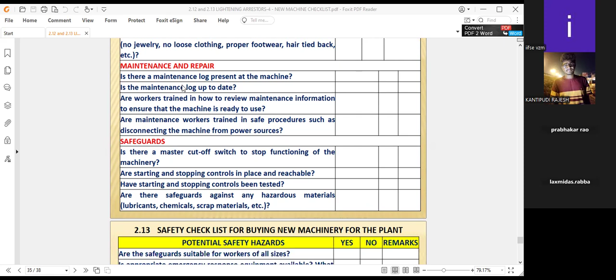That's why maintenance and repair is a very important area, and safeguards are very important. Is there a master cutoff switch, is it functioning, and are the starting and stopping controls in place and reachable? Because if the master cutoff switch is not functioning properly — suppose a circuit's ELCB is provided but not working — the master switch should immediately be cut off by the employer.